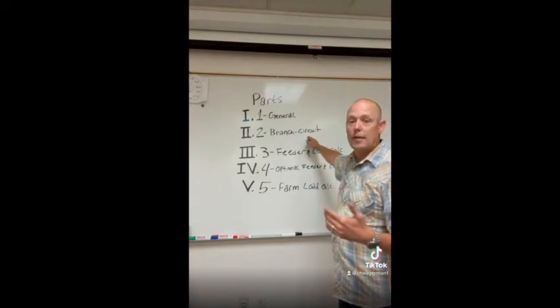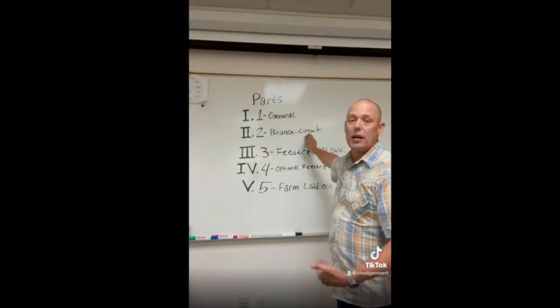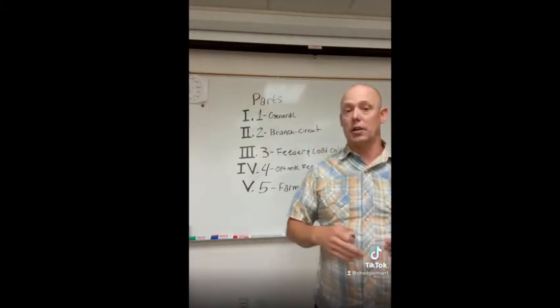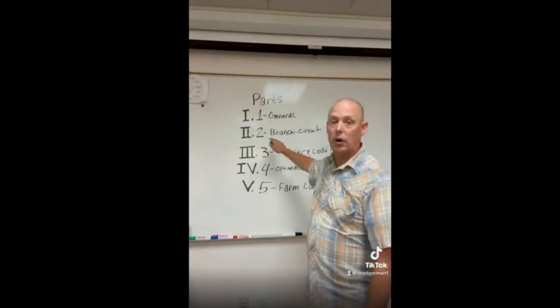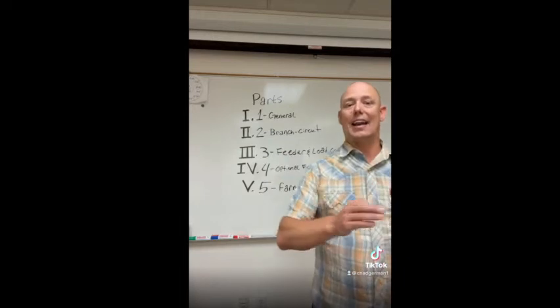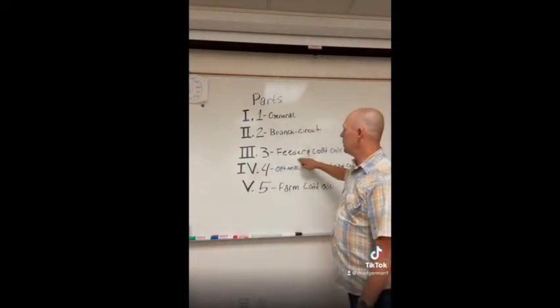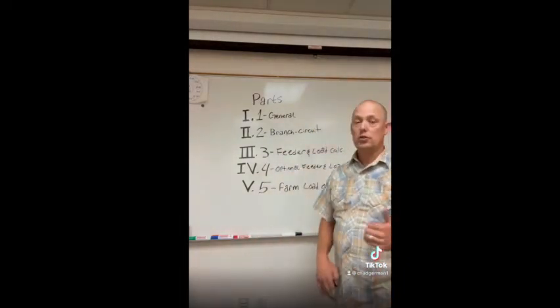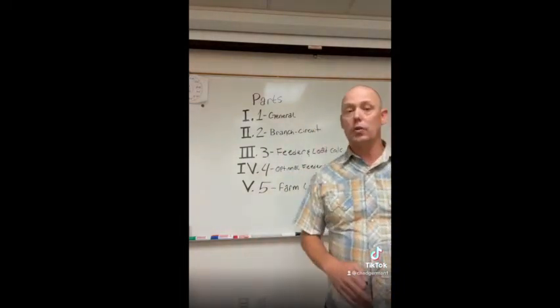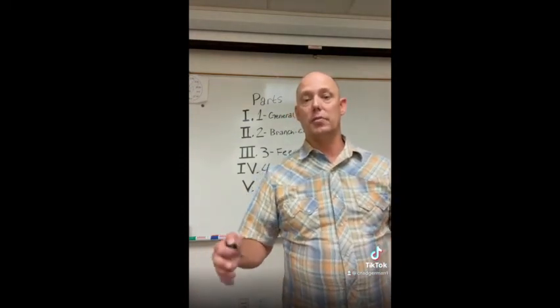If you look at what we're doing here, 220.14(G) tells us that a show window has 200 volt-amps per linear foot of show window. This is for adding a branch circuit to an existing service, because Part 2 is talking about adding a branch circuit.